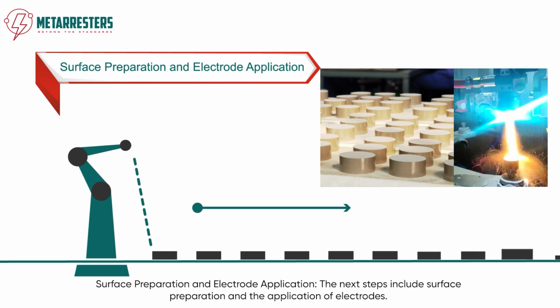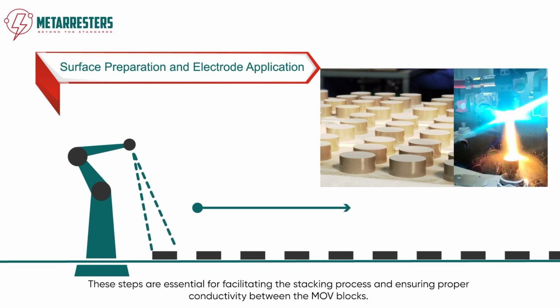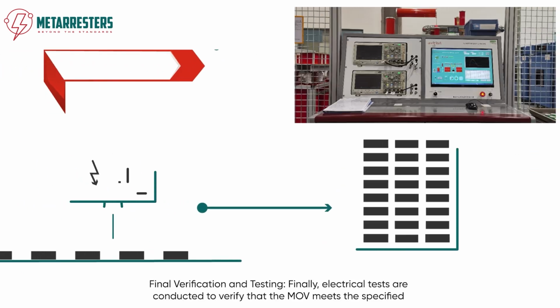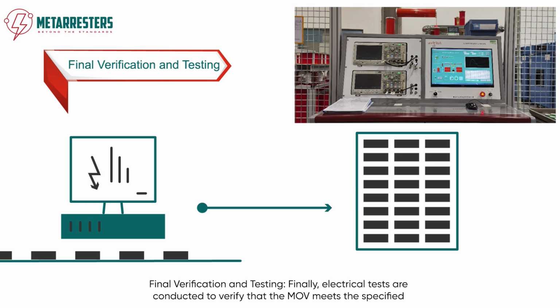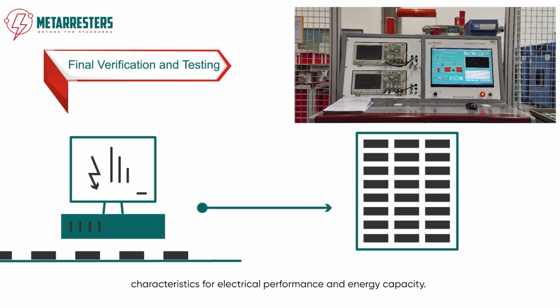Surface preparation and electrode application. The next steps include surface preparation and the application of electrodes. These steps are essential for facilitating the stacking process and ensuring proper conductivity between the MOV blocks. Final verification and testing. Finally, electrical tests are conducted to verify that the MOV meets the specified characteristics for electrical performance and energy capacity.